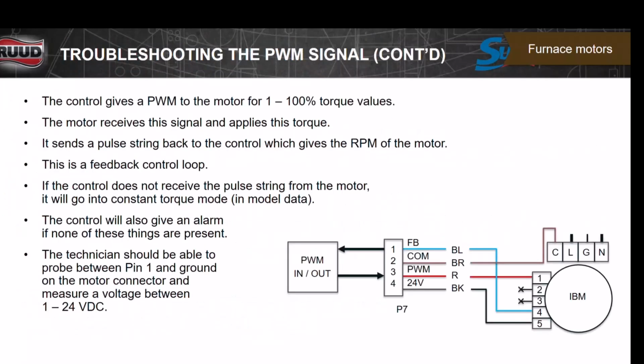Here's the typical wiring between the board and the indoor blower motor. As you can see, it looks like a regular ECM motor, 1, 2, 3, 4, 5 tap, but they're all hardwired into the plug and plugged in where you don't have to move it. That's because we changed the speed of the motor with what? The app, right? So we don't have to change anything. We can still check it, though, to see if it's putting an output on that particular terminal.